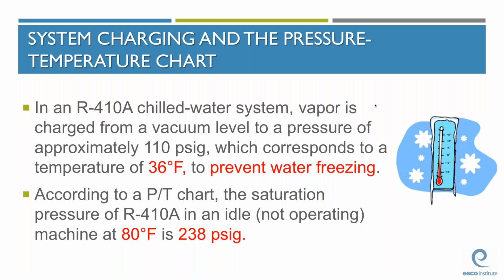On the chiller side, when charging a chilled water system that's in a deep vacuum, it's important to start charging the system with vapor refrigerant. If we charge liquid into a system that's in a deep vacuum, that liquid can flash to a vapor, and that can cause any non-moving water in the chiller barrel to freeze. So it's recommended that vapor refrigerant be added to the system until the temperature that corresponds to the system pressure is above 32 degrees Fahrenheit, preferably in the 36-degree range.